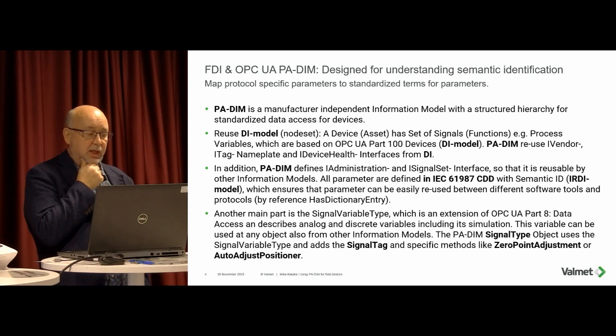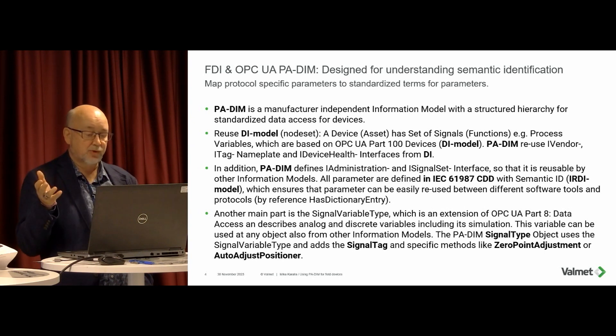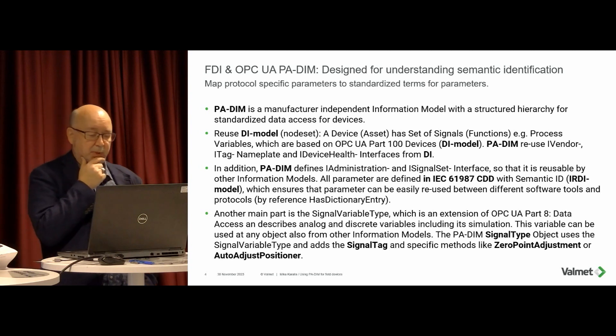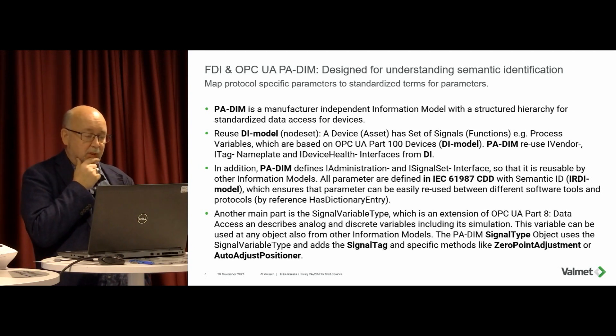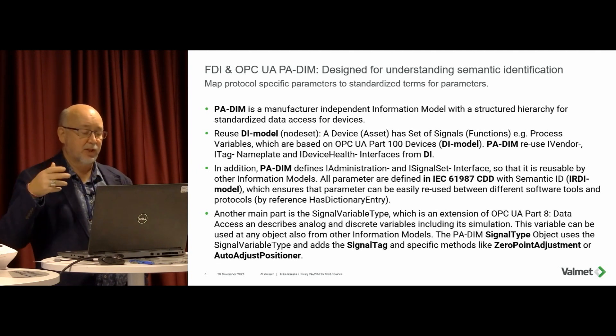PA-DIM is designed for understanding semantic identification. There is a manufacturer-independent information model that reuses the DI model and the device asset that the asset management shell can use. It also contains functions and process variables. There is the OPC UA Part 100 — I have to check that before presenting — and then an IEC specification using the IRDI model and IRDI node set. I had to do some reverse engineering to find out how the dictionary entry is used.